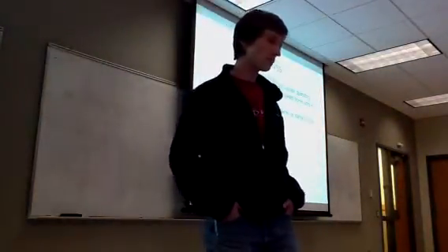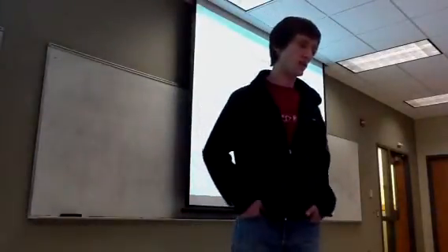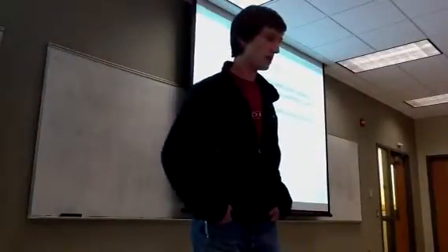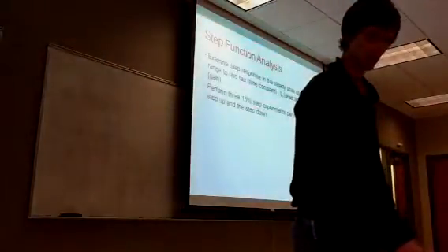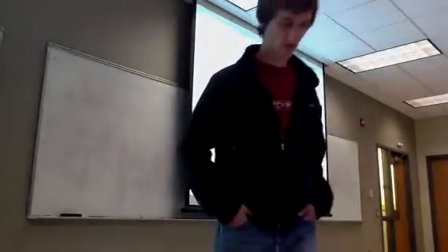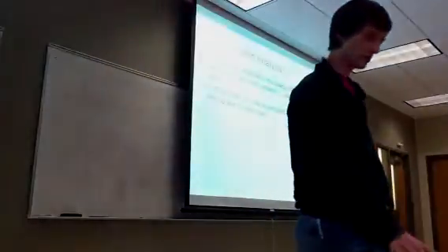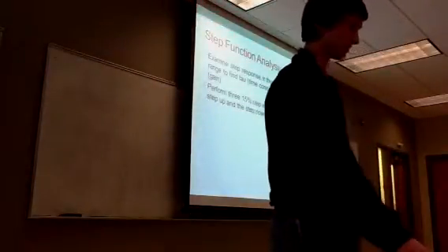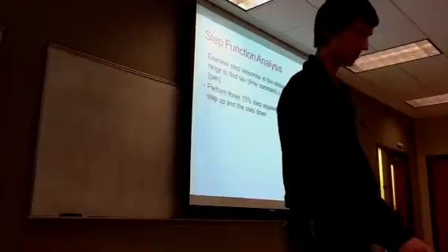After that, we worked on step function analysis. So to do that, we would examine the step response and the steady state operating range. So that would be between 65 and 100%. I think we actually went down to 55 to begin this, and we did it in 15% step increments. So we did 3 different ranges. We did 55 to 70, and then 70 to 85, and then 85 to 100. And we did 3 step ups and 3 step downs for each operating range.